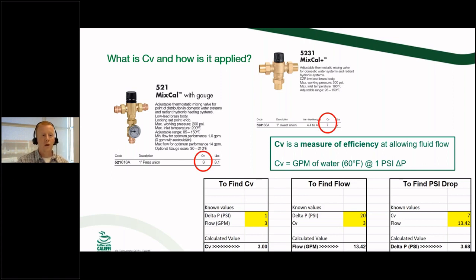And you can even see it here between the 2 mixing valves, our 521 series and our 5231 series. The difference between 3 and 7 is obviously pretty significant. And again, you're going to get more flow through that bigger valve, that 7 CV valve, with less pressure drop, and that's perfect. So how does this come into play? We talked a little bit ago about how sizing mixing valves based on pipe size really gets people into a lot of trouble. This is a perfect example. We have a little bit of overlap in our 2 models here. We have a 1-inch mixing valve in our 521 and a 1-inch mixing valve in our 5231 series. The 521 is a standard mixing valve. The 5231 is a high flow mixing valve. But you'll notice that they're both 1-inch connections, but one is a 3 CV and the other one is a 7 CV.